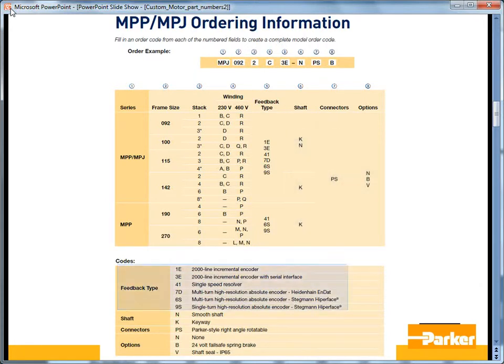The feedback type codes are as follows: 1E is the incremental encoder; 3E is the smart encoder used on the Aries drives; 41 is the resolver; 7D is the absolute multi-turn EnDat Heidenhain encoder; 6S is the multi-turn high-resolution Stegmann Hiperface SYNCOS encoder; and 9S is the single-turn Stegmann Hiperface absolute encoder.